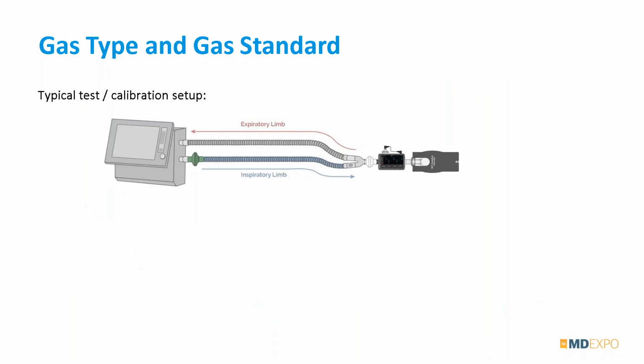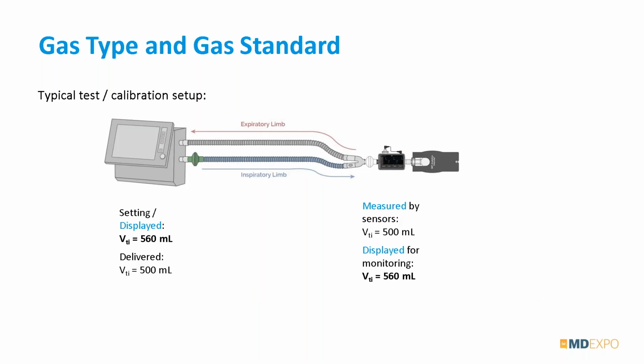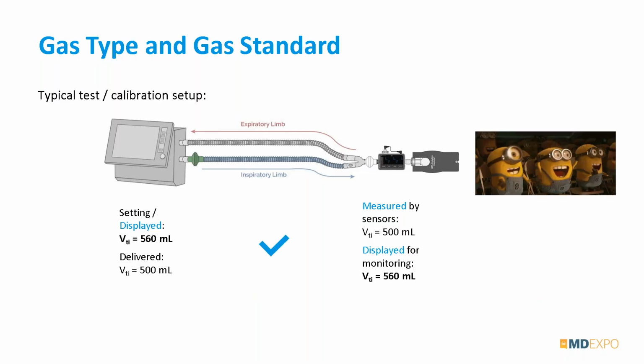Okay, so now if we have our ventilator showing BTPS, we know that it's delivering less than what's set. The analyzer is measuring that same 500 mL, but now it's going to display 560. So what we have is a match where we're actually comparing apples to apples, right? BTPS on both sides. Okay.